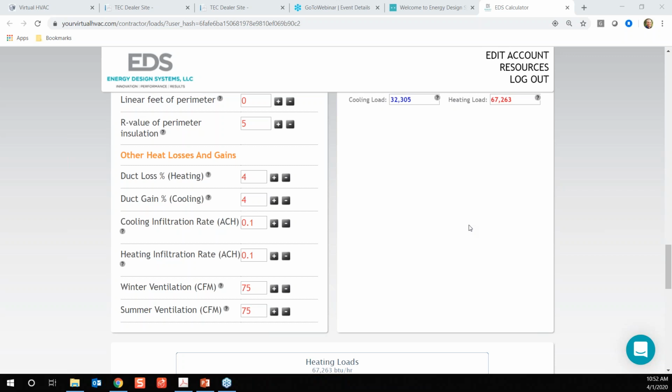When I do commercial load calcs, I put in 0 infiltration, literally 0, because in those cases, we have a pretty large ventilation requirement relative to a pretty small bathroom exhaust requirement. So it's positive pressure. Nothing's infiltrating. Stuff's actually a little bit exfiltrating, if you will. The same thing with residential. The load calc is definitely affected by that infiltration, and Doug is absolutely right. That blower door gets you the most accurate way.